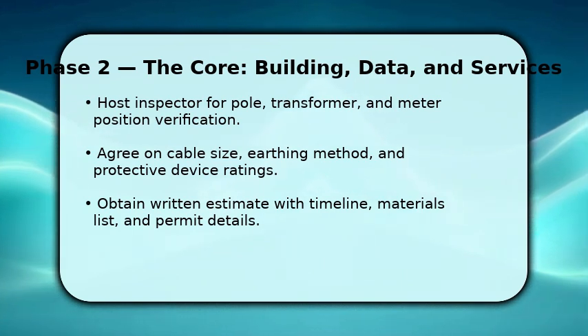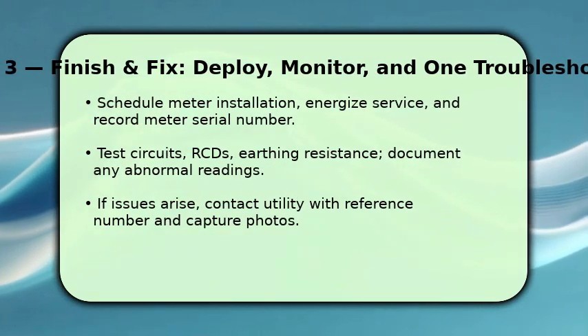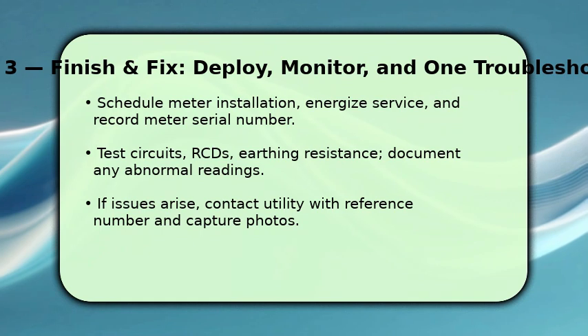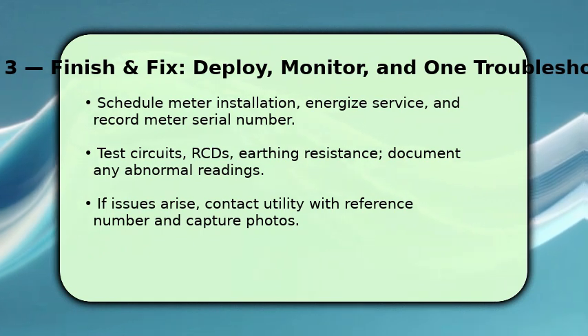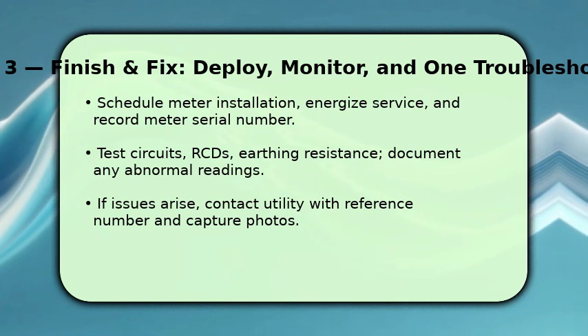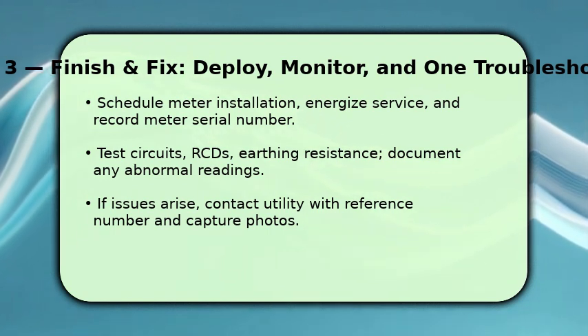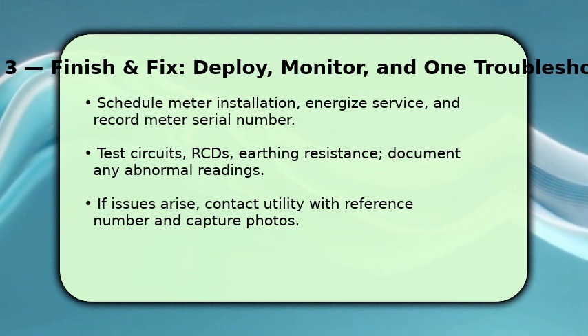You finish by having the utility install and energize the meter, verify the meter serial number and that seals are intact. Then test each circuit and safety devices, RCD, breakers, and earthing resistance, to confirm correct operation, record readings and photos for proof.